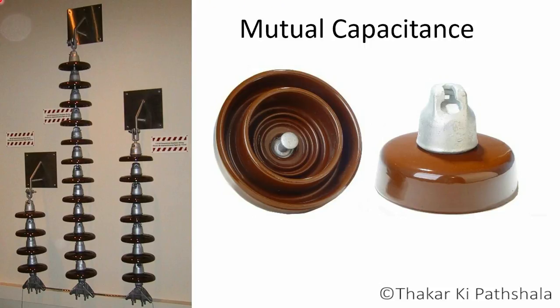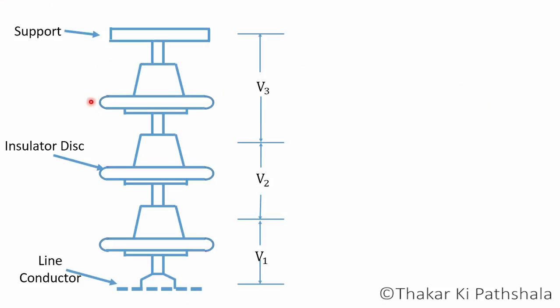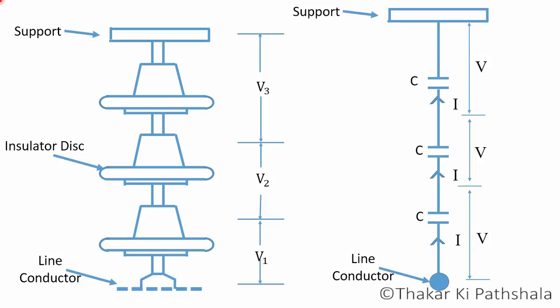This is called mutual capacitance C. As all the units are the same in shape, size, and material, the value of their capacitive reactance will be equal. So if we draw a line diagram of this system, it will look like this. Equal charging current will flow through all the discs and we can imagine that there will be equal voltage distribution.